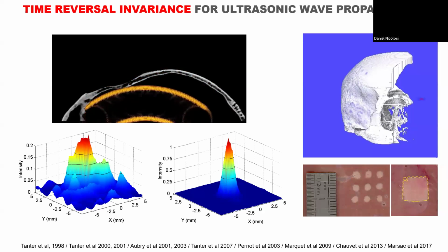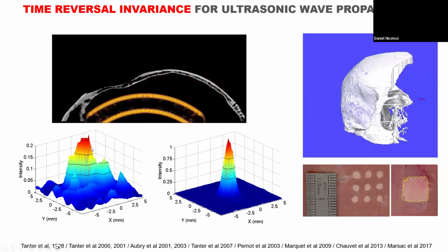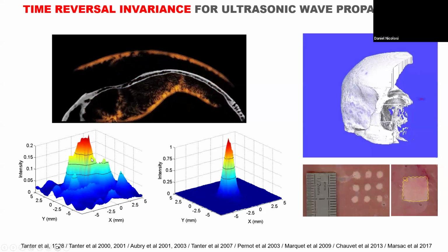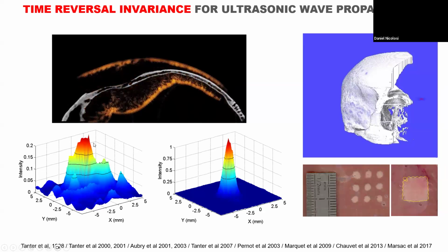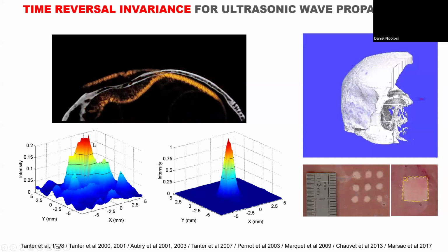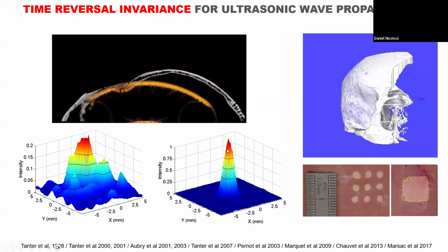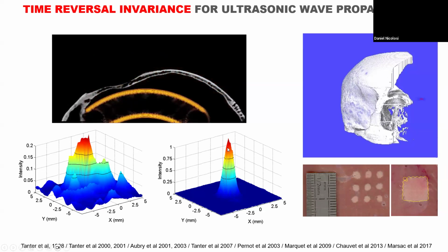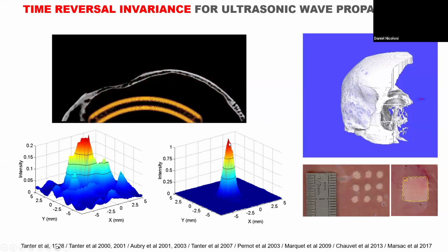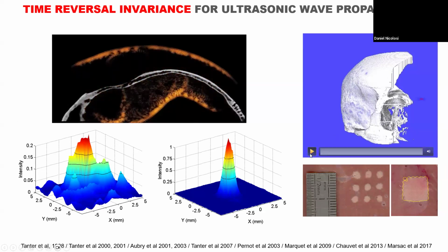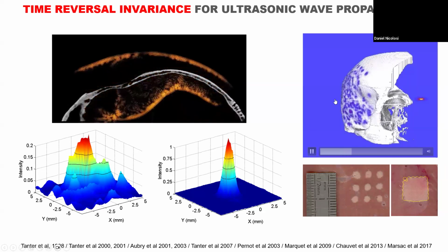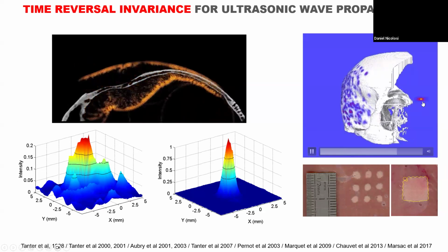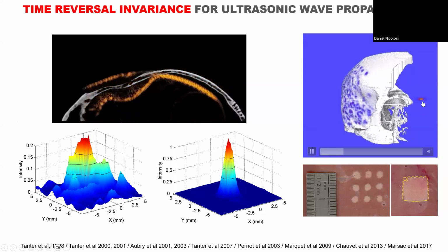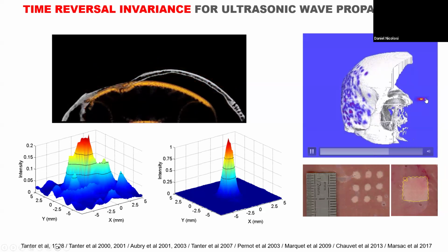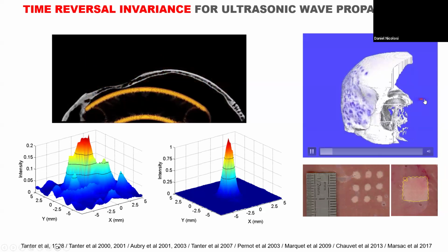on the patient. And in fact, if you do this through human skull bones, you see that without corrections, you have a bad focusing in the focal plane with a low intensity at focus because you've got destructive interferences at focus. But if you use time reversal focusing guided by CT scan, you see that you refocus perfectly with a very high amplitude here. And if you transmit during several seconds, you see that there is an increase of temperature of about, here it was about 10 degrees increase of temperature at a focal spot which has the size of a rice grain.